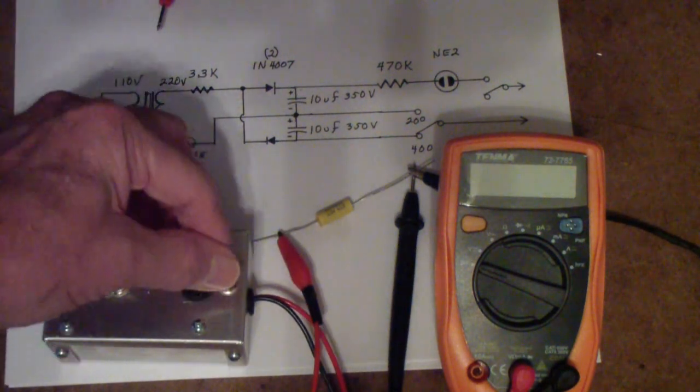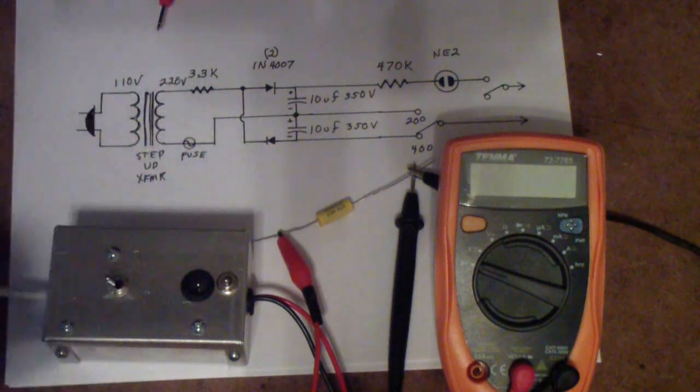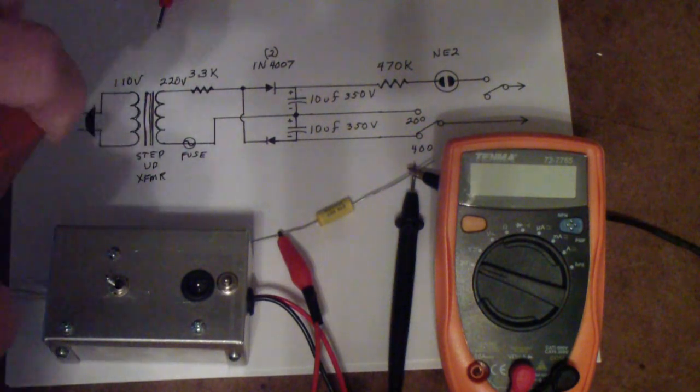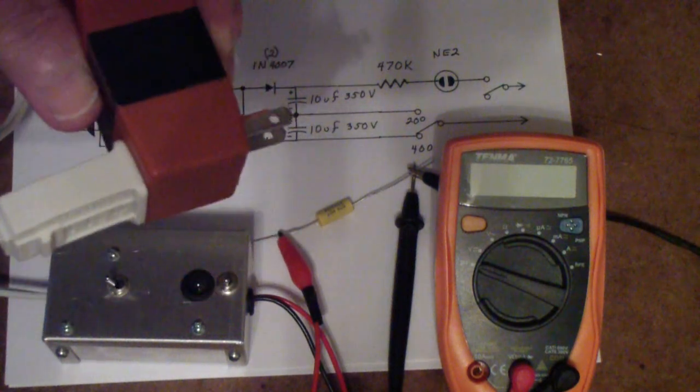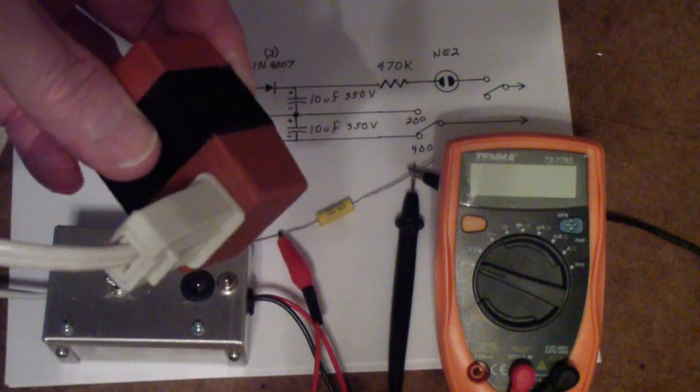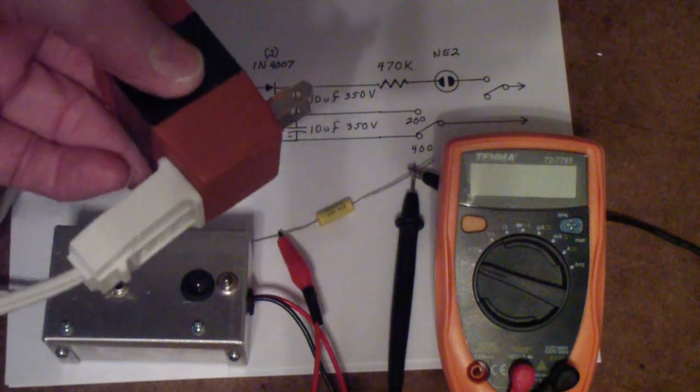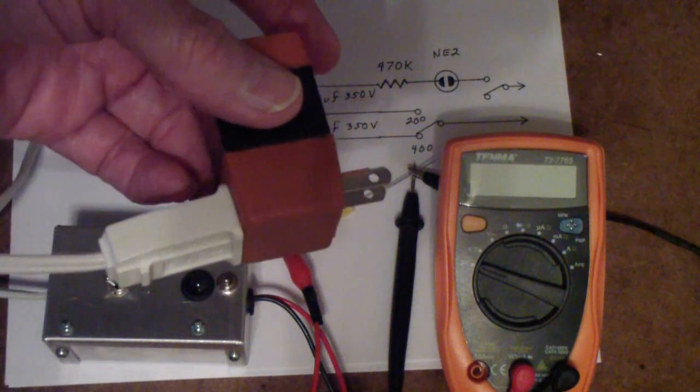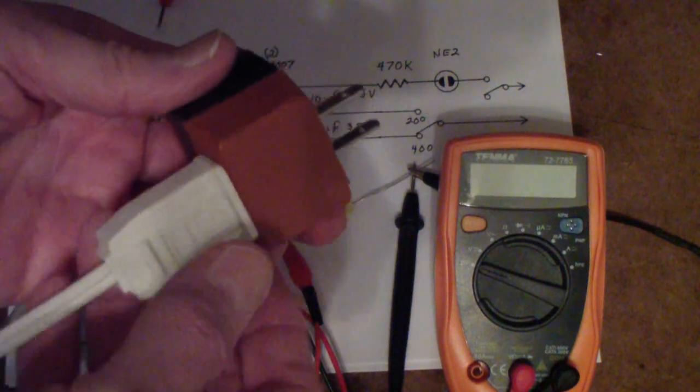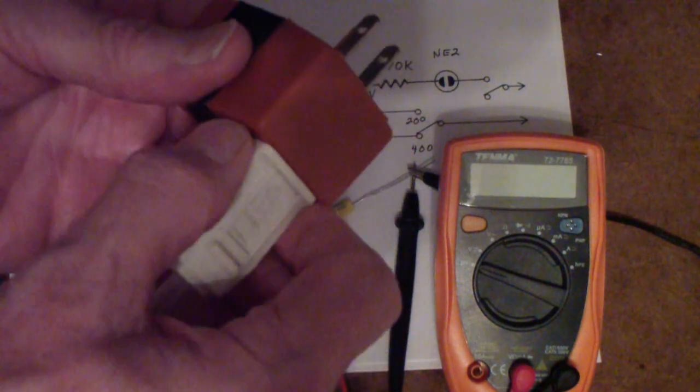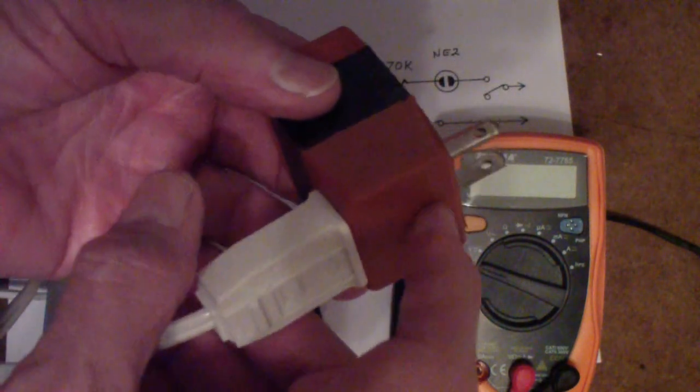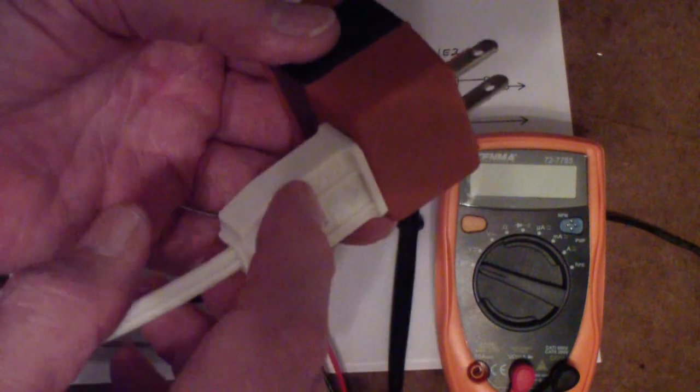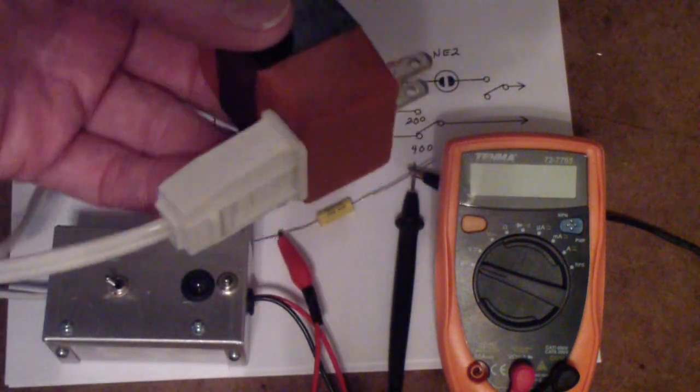I mentioned that I have a switch here which switches the voltage. What I didn't mention is that the unit plugs in to a transformer. This is an ordinary transformer that people in the U.S. use to step up 110 volts to 220 volts to operate small appliances designed to run on European current. I'll also point out that this is actually a cord off an old Christmas tree light and it has fuses in it. So not only does this provide isolation, but the fuses also protect you against primarily fire.